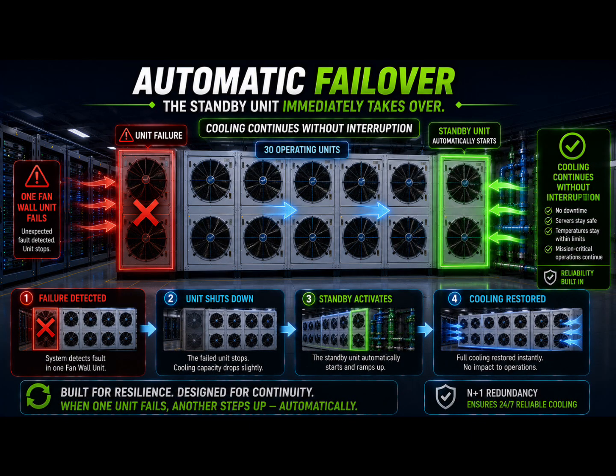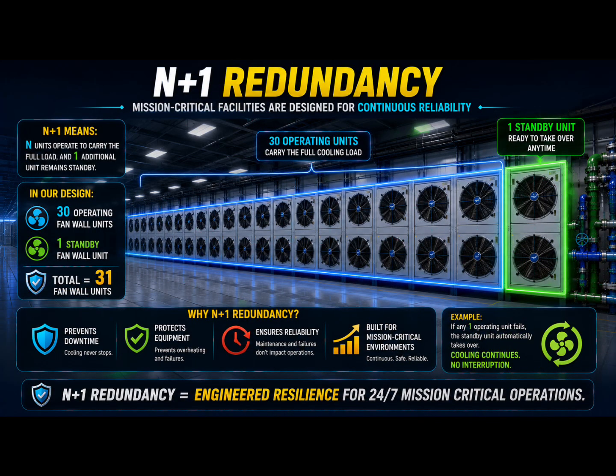That is engineered reliability. So our final selection becomes 30 operating fan wall units plus one standby unit, a total of 31 fan wall units. This is not oversized equipment. It is carefully engineered resilience.